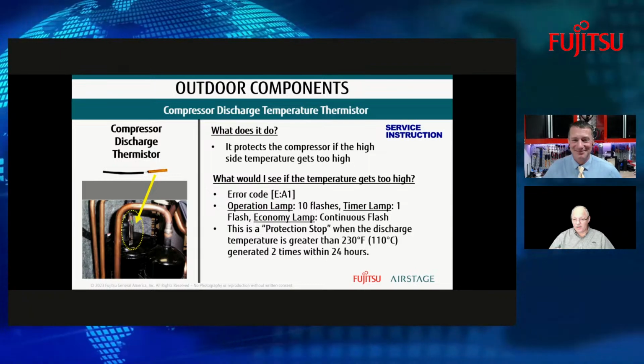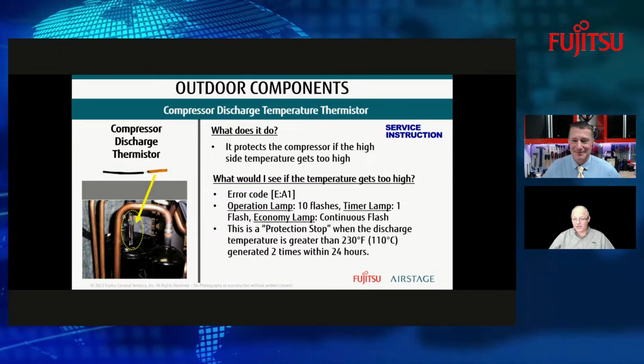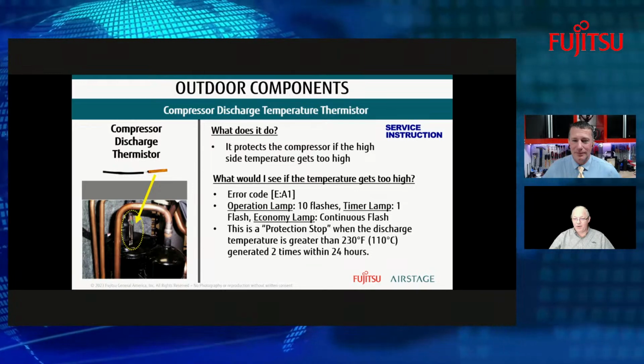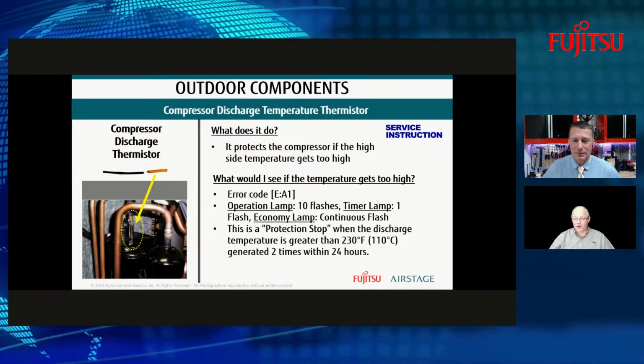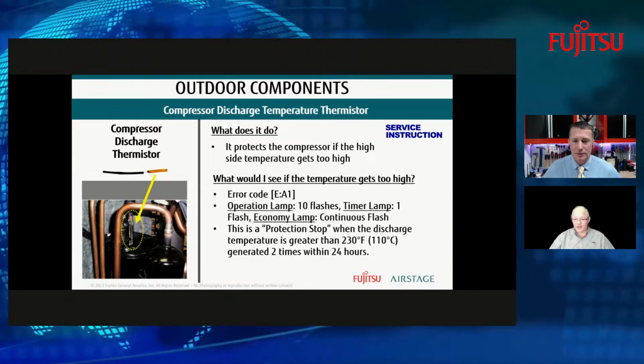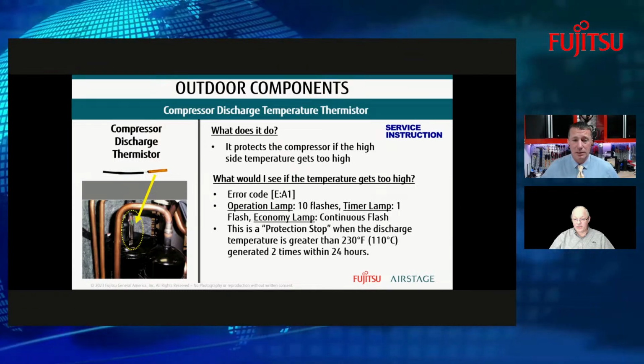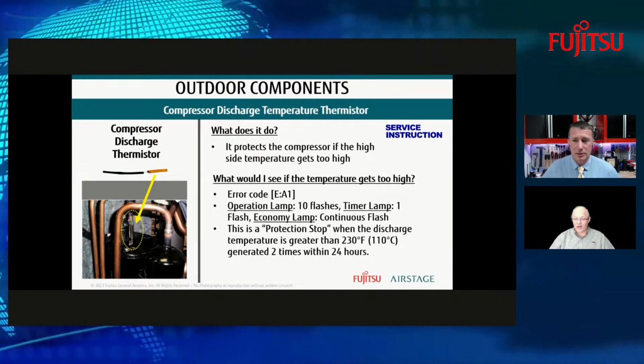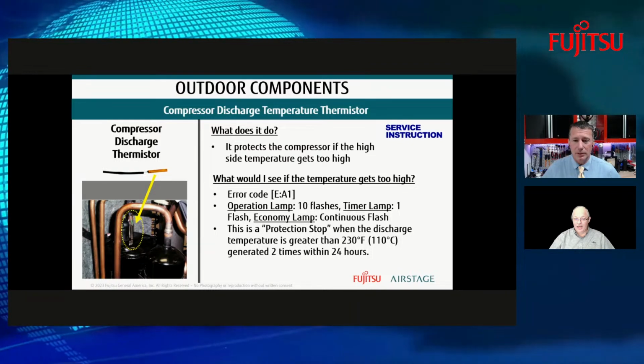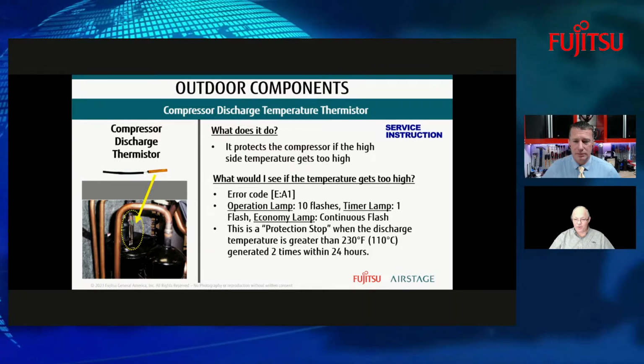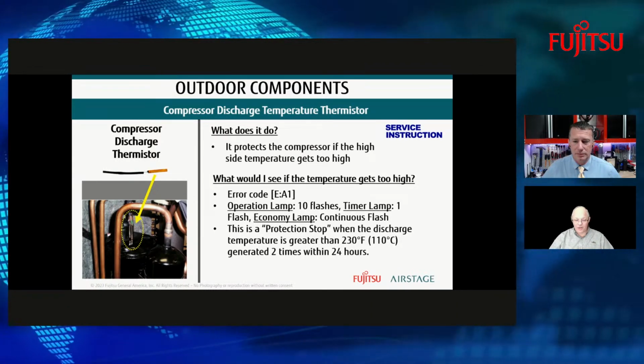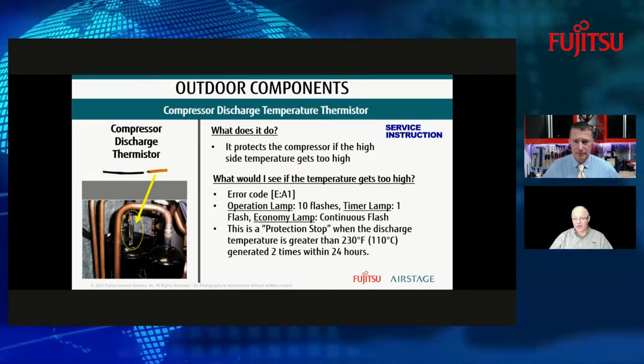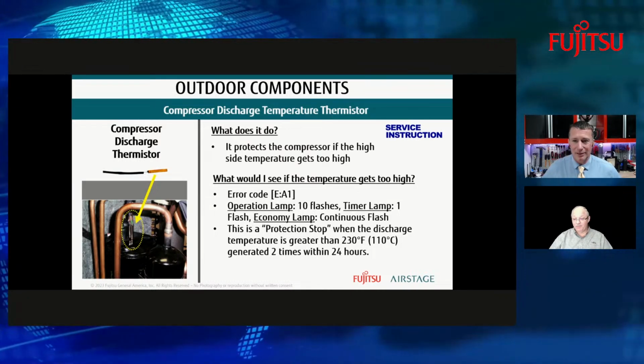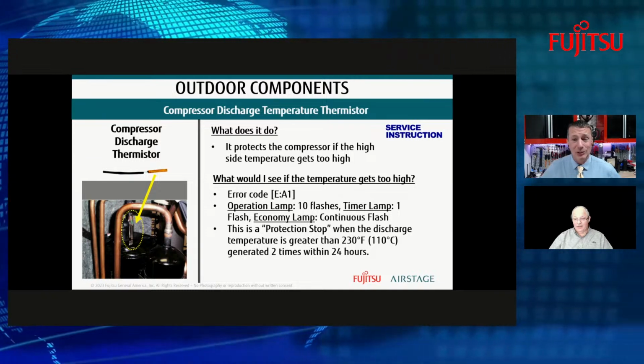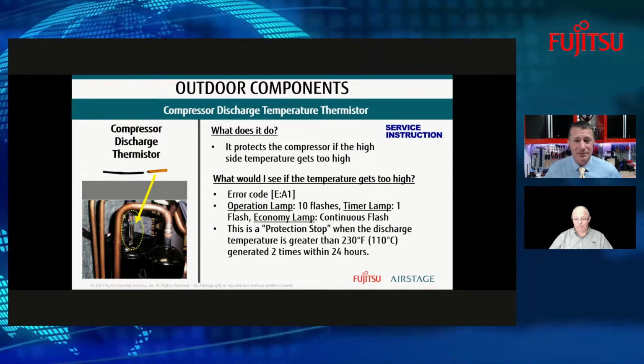And so the way this works on this particular model is you'll see that it says the protection stop is when the discharge temperature is greater than 230 degrees Fahrenheit. Okay. Or 110 degrees Celsius. And it has to be generated 2 times within 24 hours. If it counts that within 24 hours, then it's going to throw an error code up and shut the system down and give you the flash. It's going to lock out and say, hey, we're running too hot. We're not going to lose this compressor. Come take a look at me.